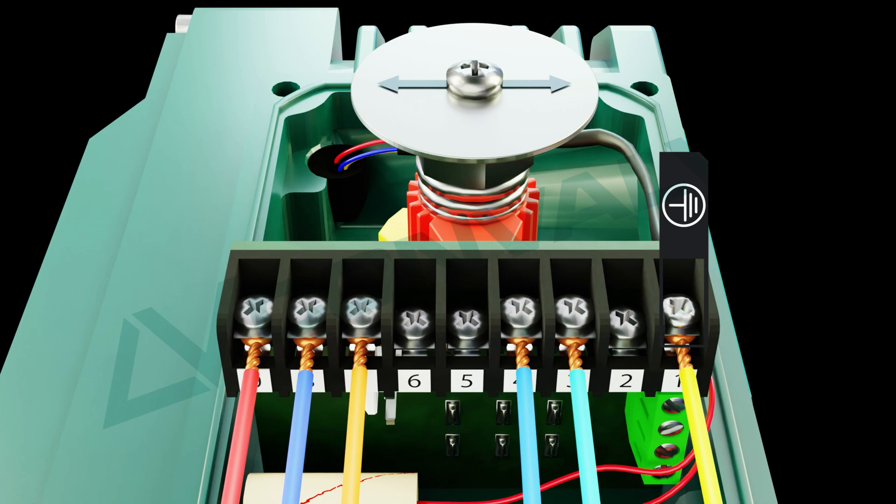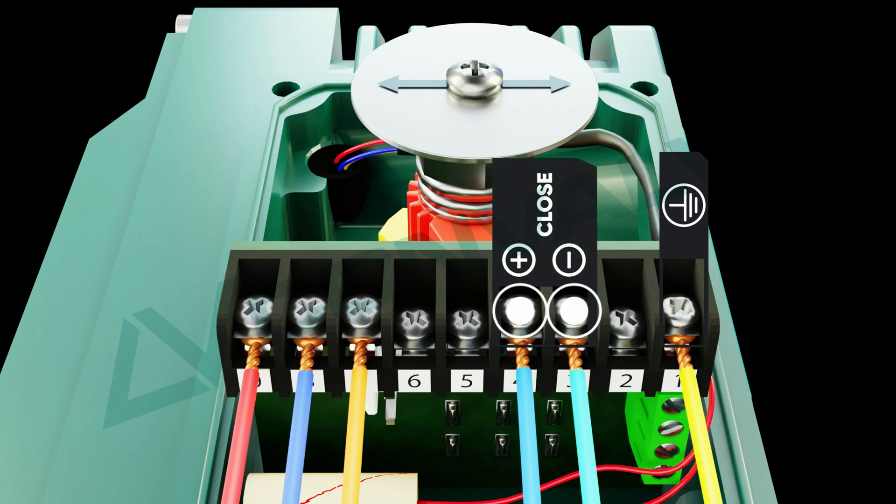To rotate or close the actuator in the clockwise direction, apply a negative DC voltage to terminal 3 and a positive DC voltage to terminal 4. The actuator will rotate clockwise until it reaches the internal limit switch and then shuts off.